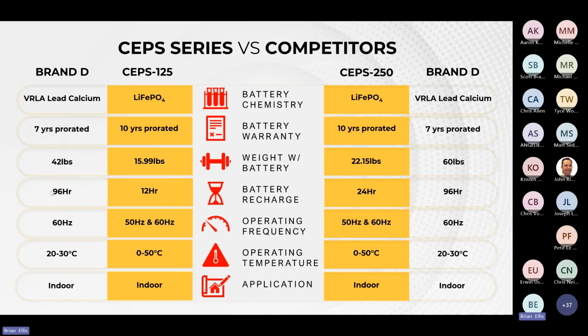12-hour recharge. Isn't it interesting? If you do your yearly full discharge test at the end of the year with the other competitor, and you have an emergency situation the next day or two, that device won't work, right? So that could be a problem. 12-hour recharge, 24-hour recharge, and then this thing's only 22 pounds. So the nice thing is it has a nice grid form factor. The plate can fit on for grid mounting on either product, and it can be wall mounted or grid mounted with the same product. You just have to buy the grid mounting hardware separate. These are meant to be indoor units.